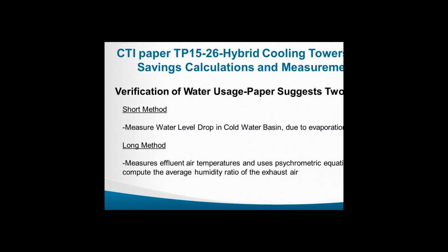The last part of the paper is measuring the water being used. One method is just measuring the basin water level drop. At the start of the test, measure the depth of the water in the basin. At the end of the test, measure the delta, and that's the actual water use. I think you could use meters to do this more accurately. It wasn't proposed in this paper, but it would be a lot more accurate. I would encourage this be part of the standard specification.